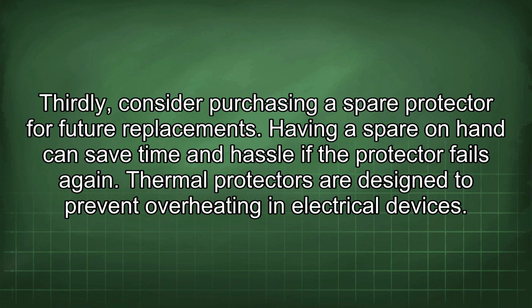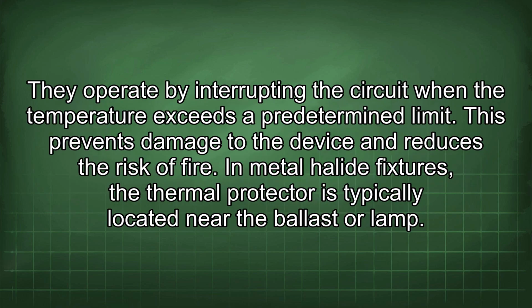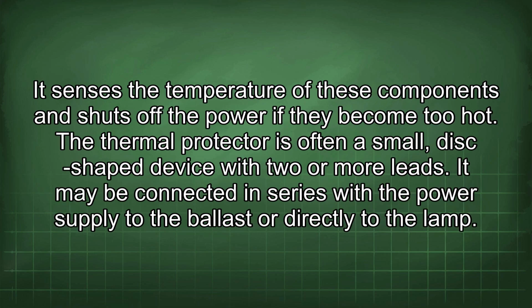Thermal protectors are designed to prevent overheating in electrical devices. They operate by interrupting the circuit when the temperature exceeds a predetermined limit. This prevents damage to the device and reduces the risk of fire. In metal halide fixtures, the thermal protector is typically located near the ballast or lamp. It senses the temperature of these components and shuts off the power if they become too hot. The thermal protector is often a small, disc-shaped device with 2 or more leads. It may be connected in series with the power supply to the ballast or directly to the lamp.